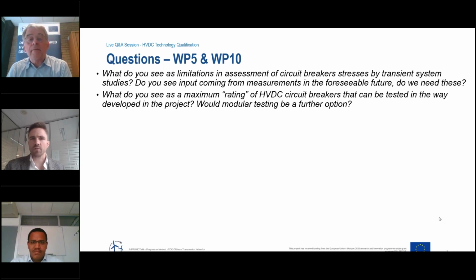So that's also different from testing valves, where modular testing is quite common. Yes, in valves, you have the same components repeated one after the other, and there are also some redundancies that you introduce. But here, the number of modules that you put in series in DC circuit breakers is not as large as in valves. So it's a different approach. It's a little bit tricky here. Well, if you prove a concept, you can work on modules. Good. I would like to close this point and go over to another question.